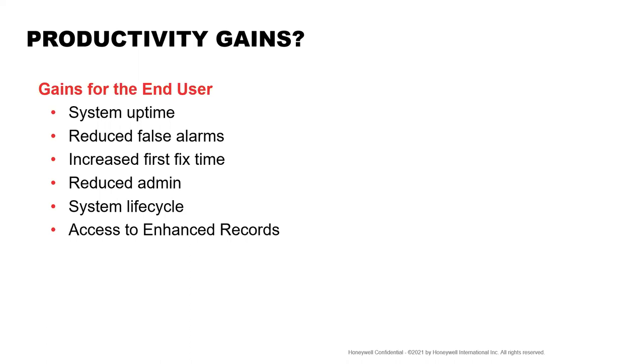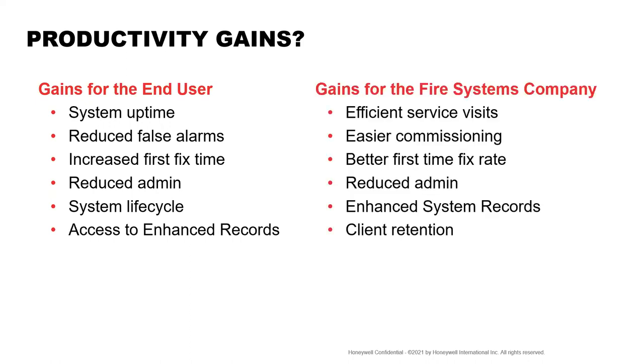The system life cycle, obviously, as we've spoken about, gives you a better idea of the condition of your system. This is a life safety system after all. You'd have your boilers looked after if you could smell gas, whatever. The same thing. This is a life safety system and it needs to be looked after. And access to enhanced records, not just the same records that we get now, but we can give you better information and clearer information. And they're untamperable and they're all automatically generated.